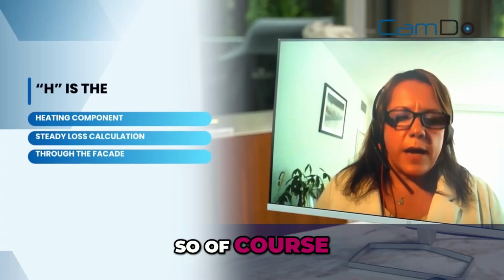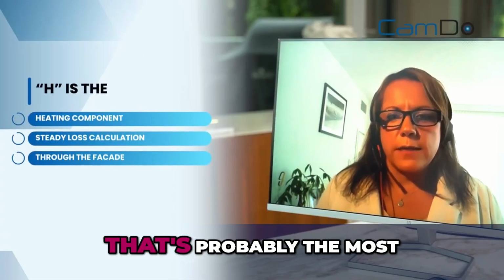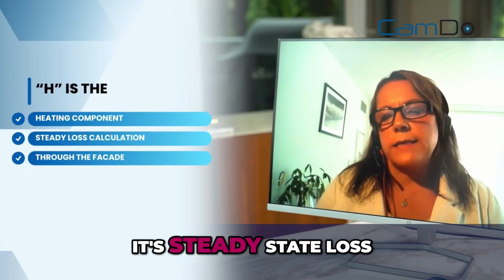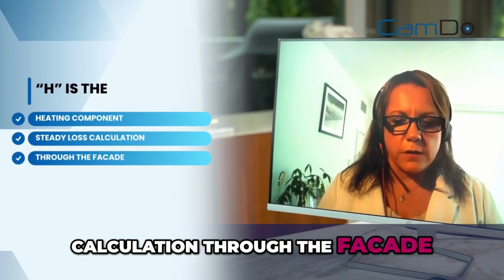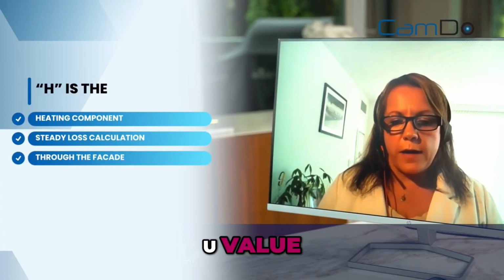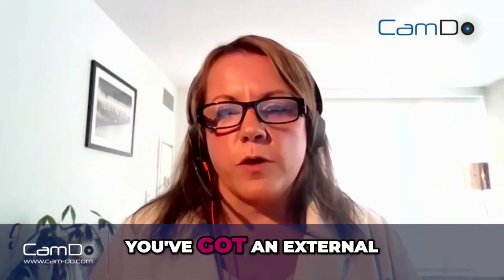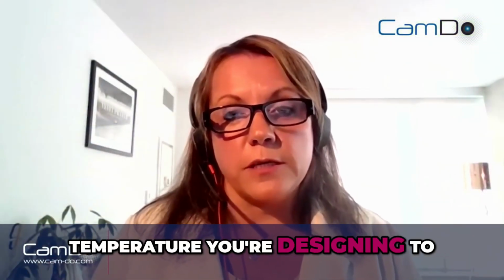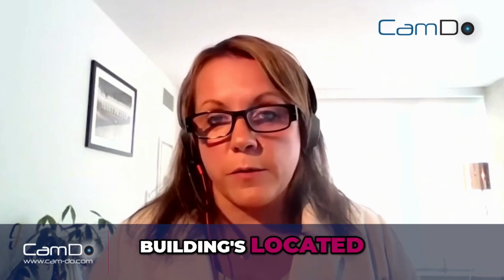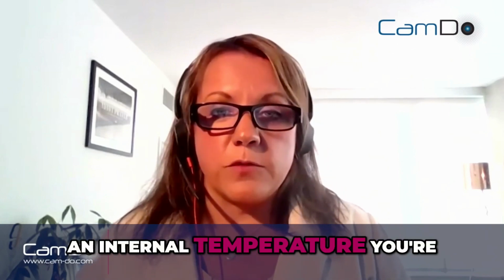So, of course, H is the heating component. That's probably the most straightforward. It's a steady state loss calculation through the facade. You've got a U value, the thermal transmittance of however well insulated your building is, an external temperature you're designing to, dependent on where your building's located, and an internal temperature you're trying to achieve. So that's quite a steady state calc.